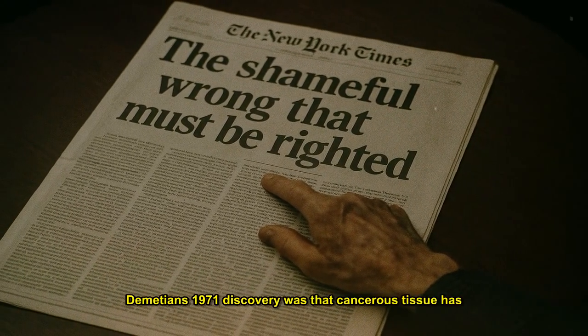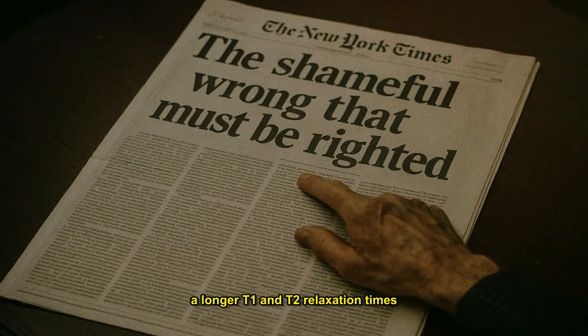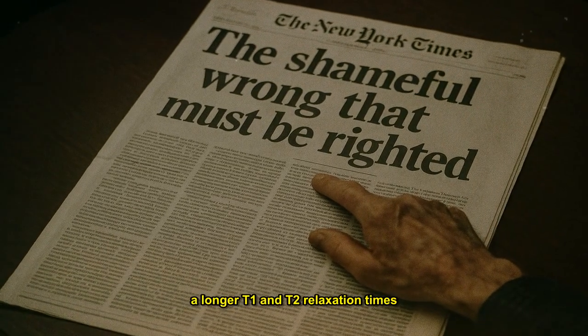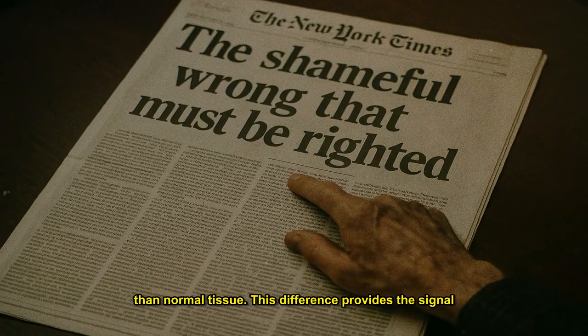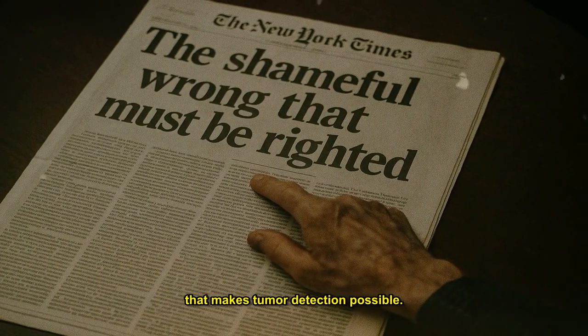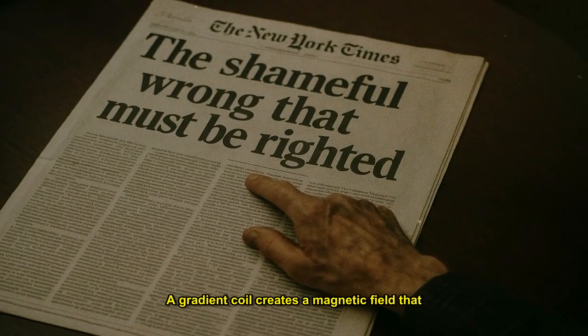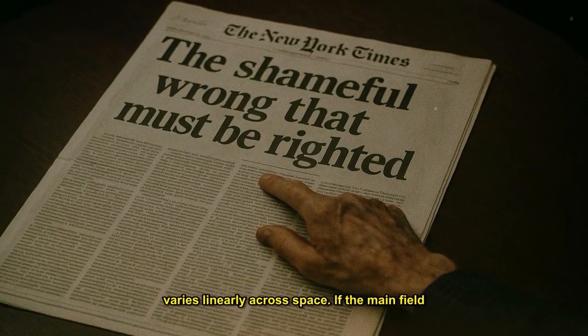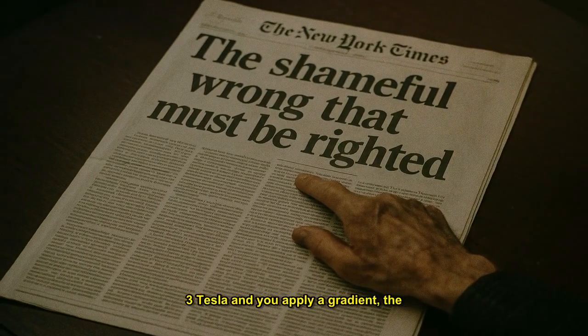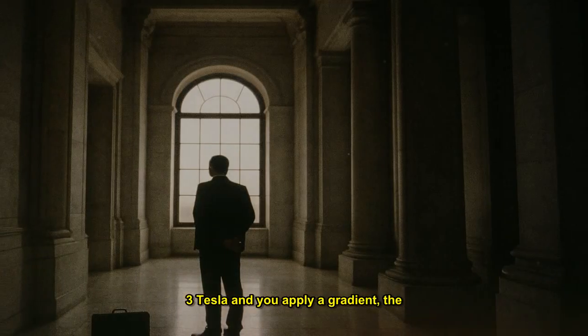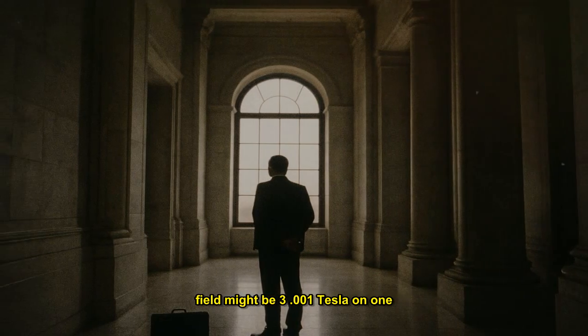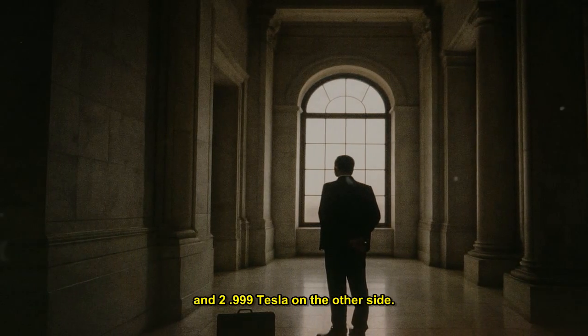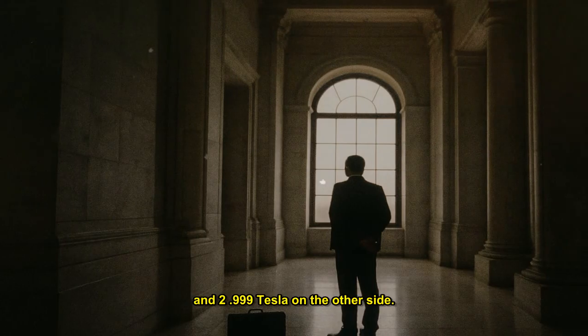Damadian's 1971 discovery was that cancerous tissue has longer T1 and T2 relaxation times than normal tissue. This difference provides the signal that makes tumor detection possible. A gradient coil creates a magnetic field that varies linearly across space. If the main field is 3 Tesla and you apply a gradient, the field might be 3.001 Tesla on one side of the patient and 2.999 Tesla on the other side.